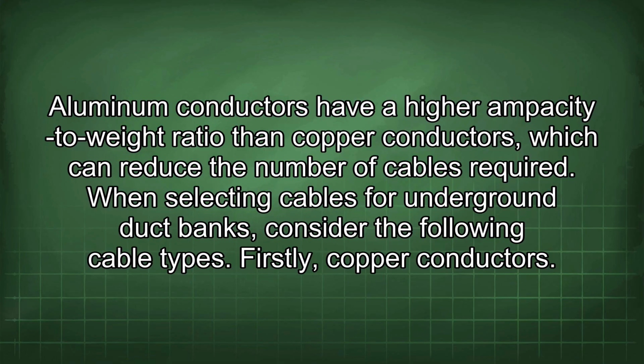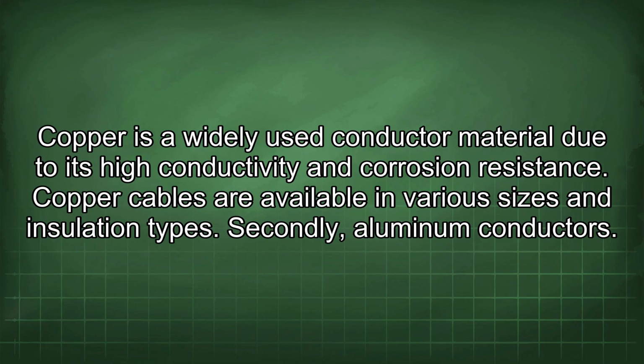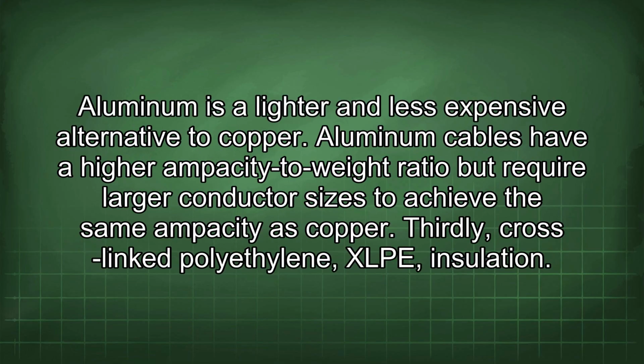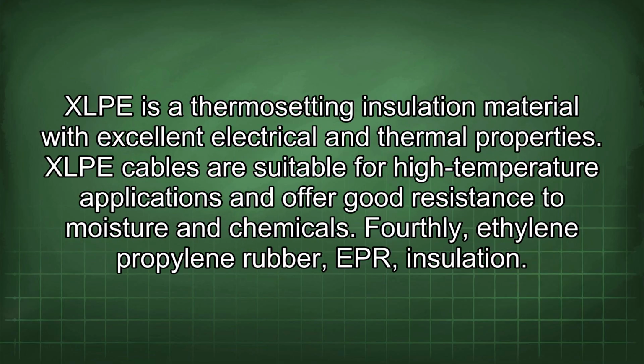Firstly, copper conductors. Copper is a widely used conductor material due to its high conductivity and corrosion resistance. Copper cables are available in various sizes and insulation types. Secondly, aluminum conductors. Aluminum is a lighter and less expensive alternative to copper. Aluminum cables have a higher ampacity to weight ratio but require larger conductor sizes to achieve the same ampacity as copper. Thirdly, cross-linked polyethylene (XLPE) insulation. XLPE is a thermosetting insulation material with excellent electrical and thermal properties. XLPE cables are suitable for high-temperature applications and offer good resistance to moisture and chemicals.